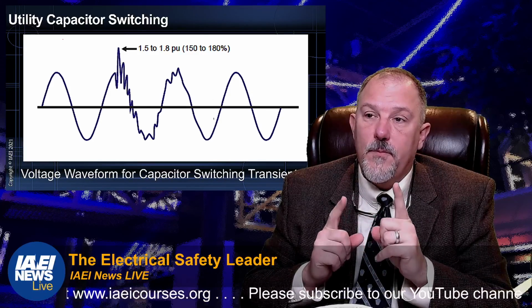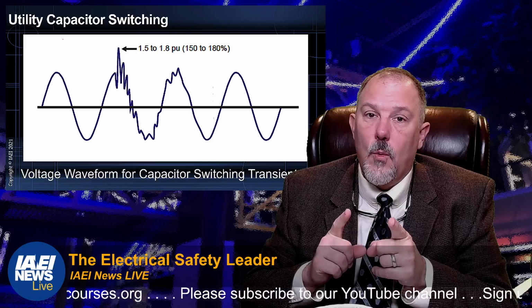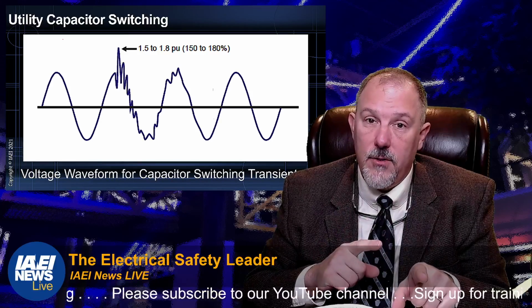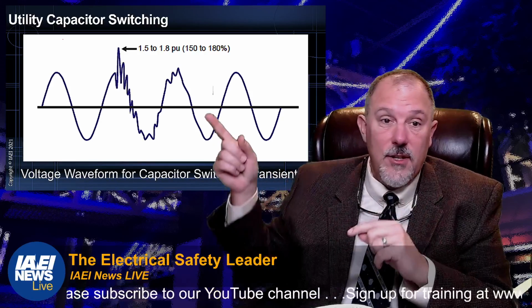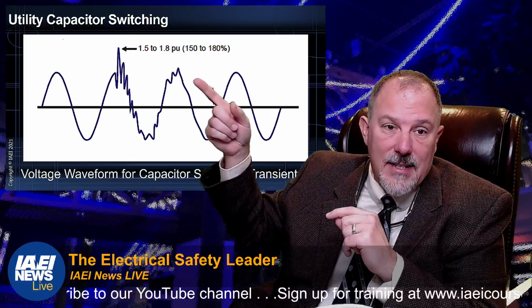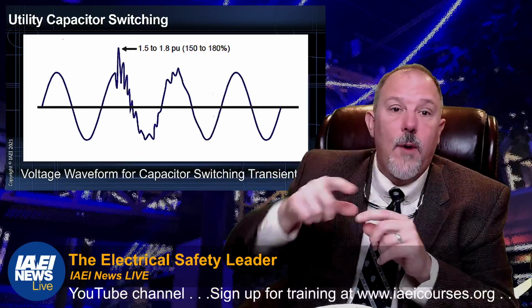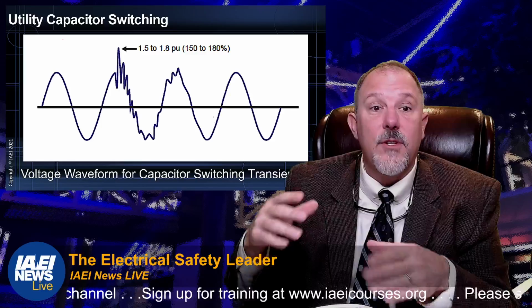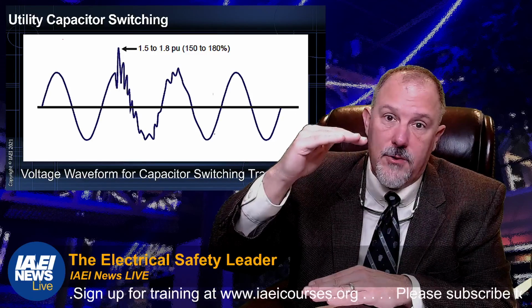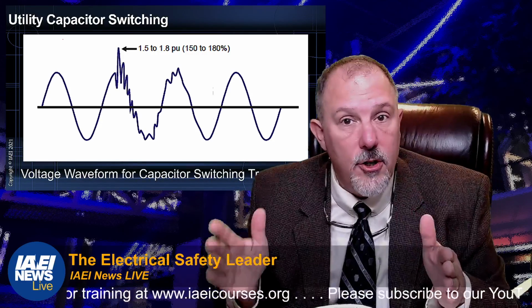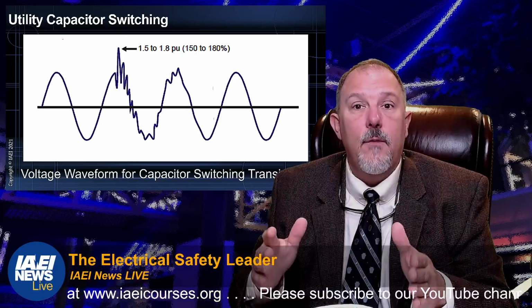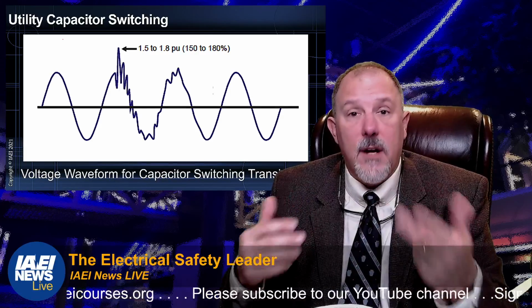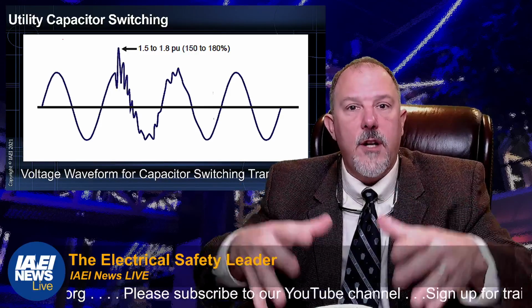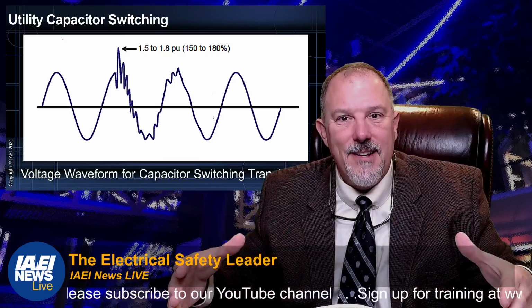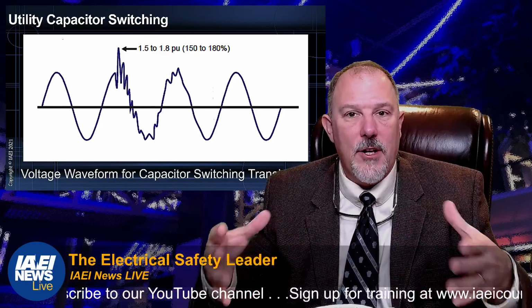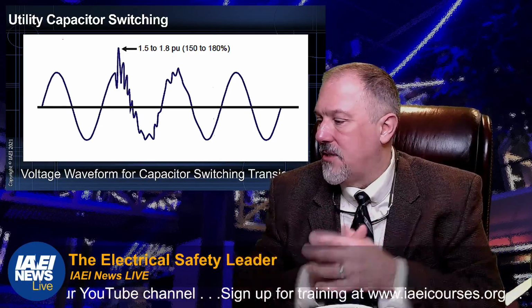Those surge strips were presenting a ground fault for a pretty good duration, because you look at that sine wave and that ring wave, and this isn't from that event, but it was very similar. It was much more pronounced. And it was a longer transient event that was occurring, and for a couple of reasons. There weren't enough homes brought onto these transformers, and there wasn't a lot of load, etc.